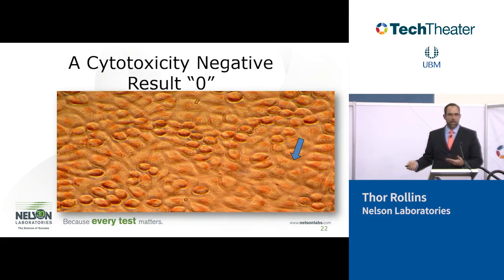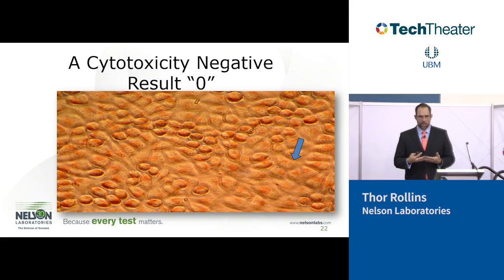That's what we want. But cytotox is great for changes because, like I said, we can evaluate a small change by looking at the impact with a relatively quick and inexpensive test. Okay? So if you have less than that 10% patient contacting change, cytotox is a great way to evaluate that, if that change is using materials that are well categorized in the medical device field.